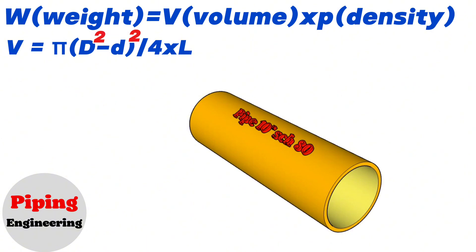This formula applies for all pipe sizes. We will explain the calculations in this video using a 10 inch and a 16 inch pipe example. Let's calculate the weight of a 10 inch pipe with a schedule 80 thickness and a length of 2 meters. To estimate the volume of the pipe piece, let's look at the wall thickness of a 10 inch schedule 80 pipe from the steel pipe dimension chart.